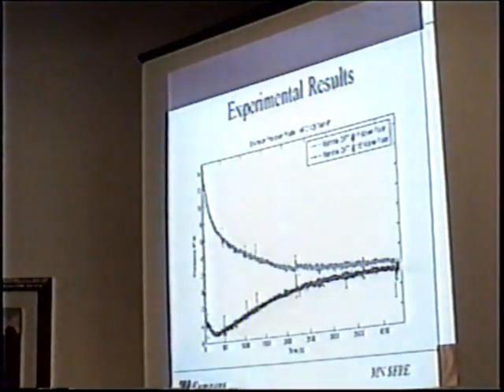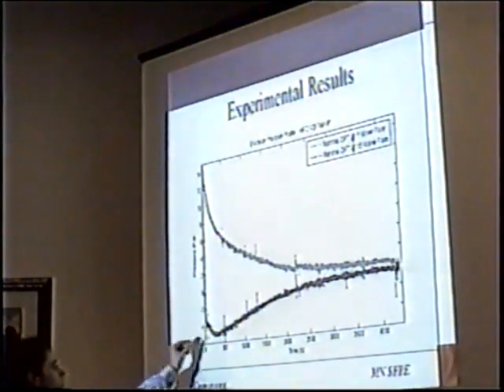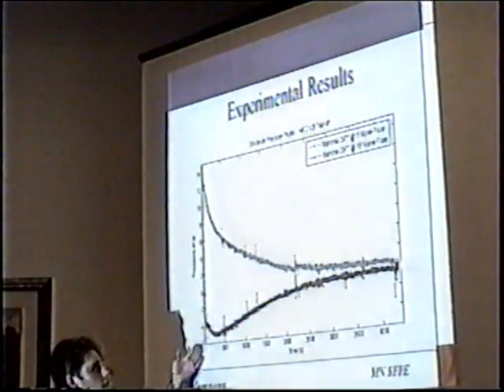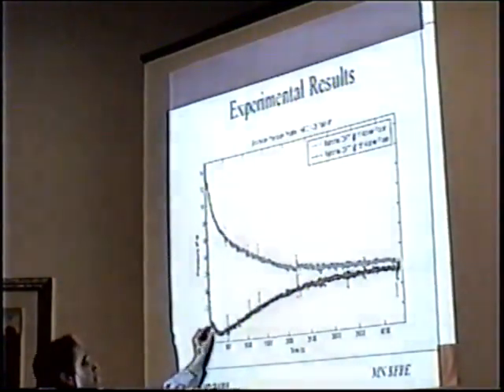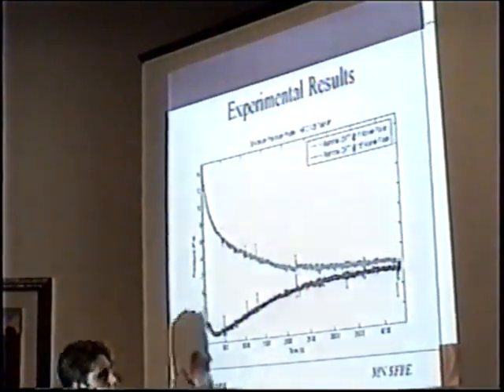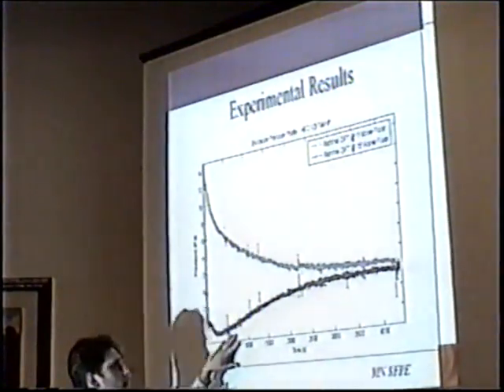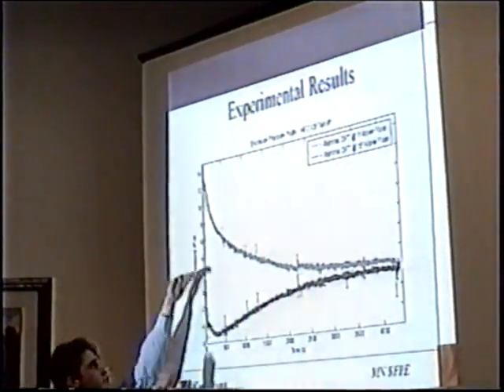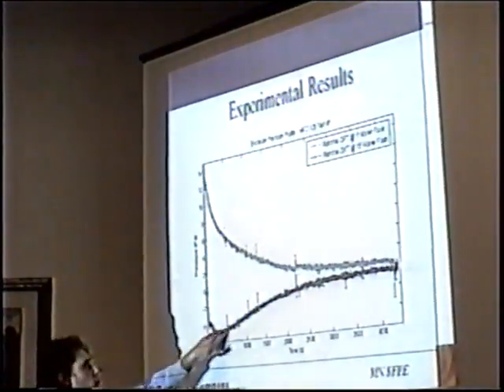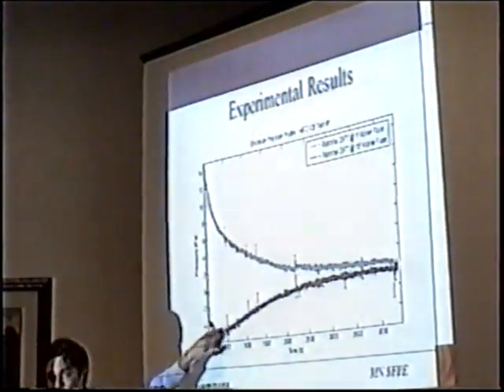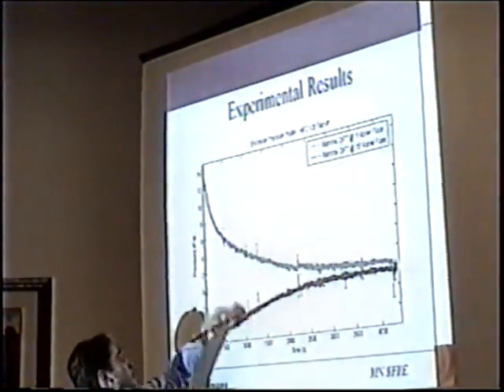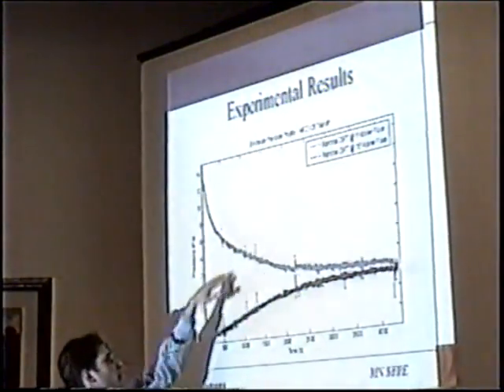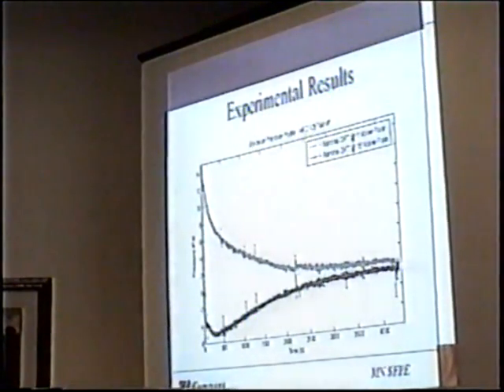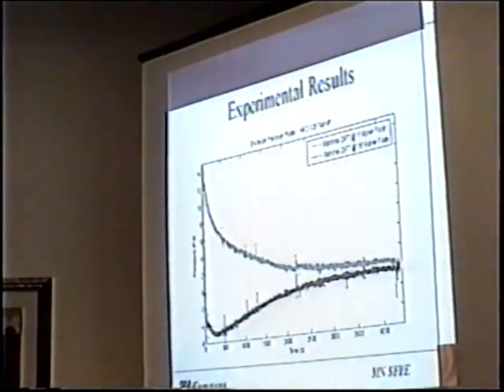At the end, though, this essentially is our agent discharge right here. This, again, is pressure versus time. Here we can barely even see our discharge, but throughout 4,000 seconds of time, this is essentially looking at the whole time. We've got 2 different pressure gauges here. This one, the low pressure, is at the top of the enclosure where there's a negative vacuum sucking fresh air into the room, positive pressure down low in the room. So this is the type of behavior that's actually driving the agent out of the room. That's just the raw force of it right there that we're looking at.